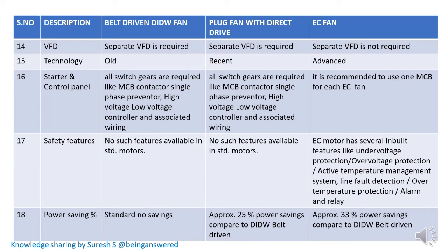For safety features, there are not many safety features available in belt driven DIDW fan, and similarly plug fan also won't have many safety features. But in EC fan, there are so many inbuilt features available: over voltage, under voltage, active temperature management system, line fault detection, over temperature protection, alarm and relay, etc.